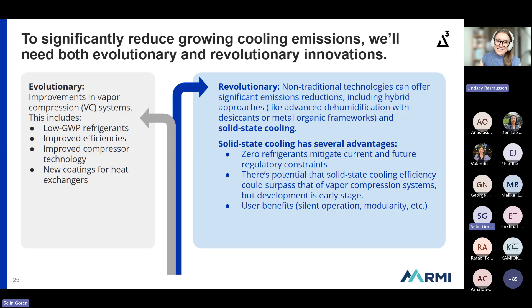Speaking to these efficiency gains, there's a lot of potential with solid state cooling to produce highly efficient systems, as the key driver is that it's not dependent on moving heat between reservoirs the way vapor compression cycles are. In the HVAC space, efficiency is often measured by coefficient of performance, or COP. Though this isn't a perfect measurement of a system's efficiency, it essentially shows how much heat or cooling a system can produce per unit of energy it consumes. The average AC on the market is close to a COP of 3, with a bit of a range, but best-in-class ACs on the market are reaching COPs closer to 5 and 5.5.